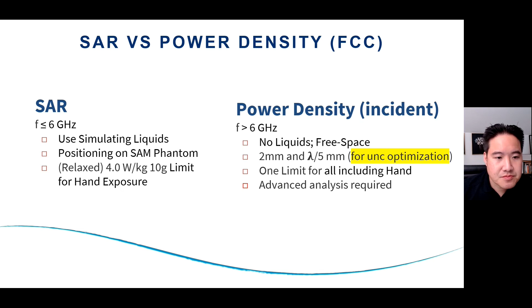And I know for those labs using DASY systems that this company is working on an update to improve the software handling of the measurement uncertainty. But for now, we're measuring two separate distances to account for the uncertainty aspects. And a note related to the hand and extremity, the PD measurements actually don't have a similar relation for the hand, which will be problematic for devices like smartphones that require a lot of simultaneous transmission, summation calculations. So that's something to keep in mind.